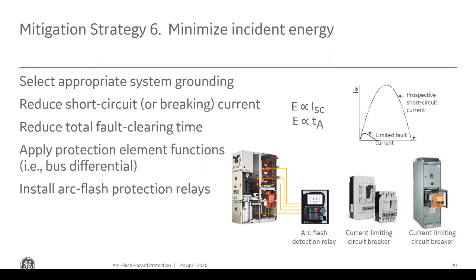There are many ways of reducing short circuit current, either by reducing the amount of short circuit current or the time it is present on the system, such as current limiting fuses and using reactors to reduce the short circuit current. For reducing the fault clearing time, install faster breakers. You can get 2 to 4 cycle breakers these days, maybe even 1 cycle breakers depending on the voltage level. Obviously, it also depends on cost, so all of these require some sort of cost adder.